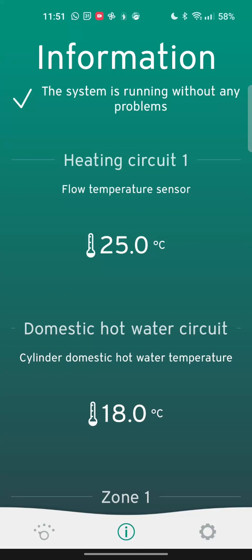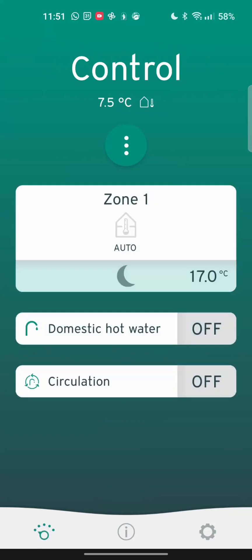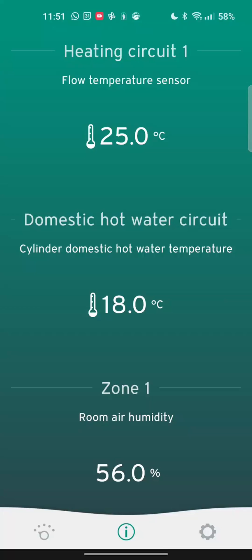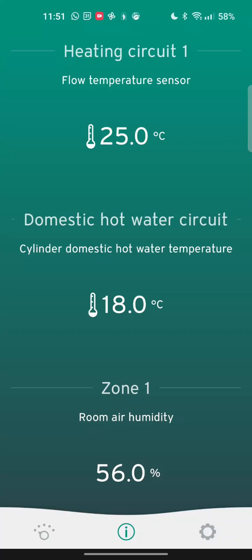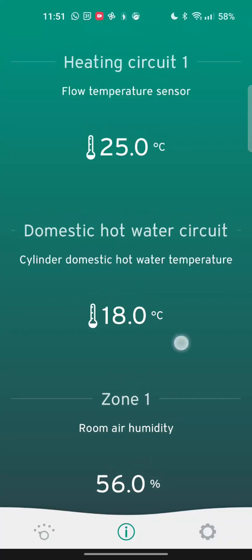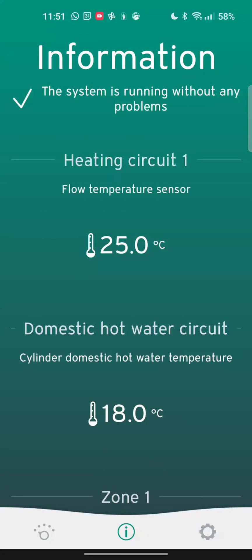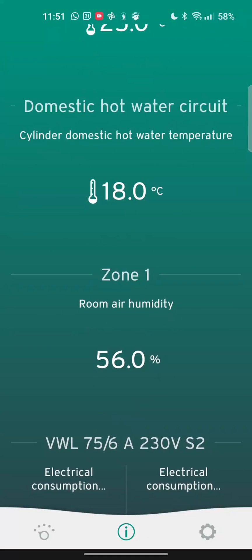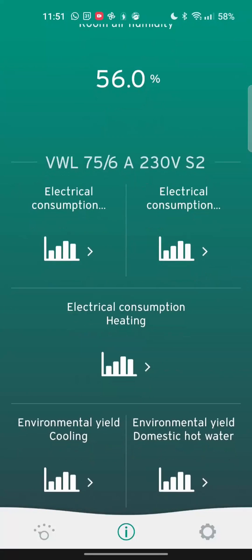What else have we got on here? Click on the information tab. You can see that this is incredibly slow to update. Our hot water cylinder after a couple of showers is saying 18 degrees. Don't pay any attention to the temperature at all. The probe is about a third of the way up. Our flow temperature is the current temperature of what is flowing around our radiators. And the heat pump will modulate that based on the temperature outside. And the room air humidity, we saw that on the other page as well.